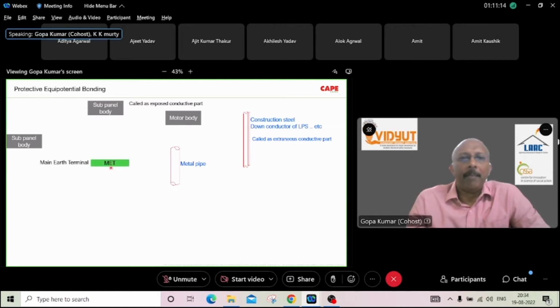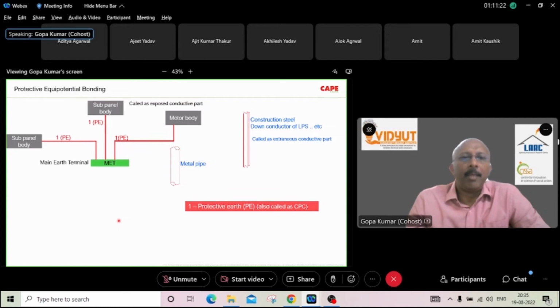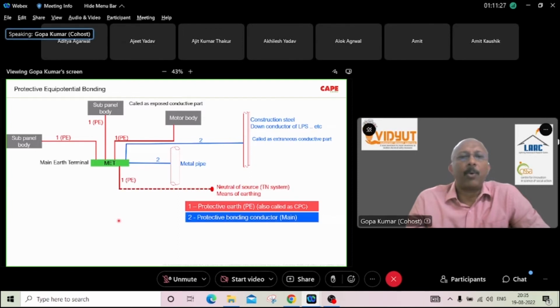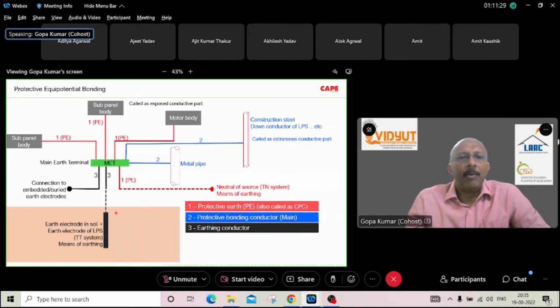You have to take a bus bar and interconnect the exposed conductive part to the MET. This is called protective earthing. Interconnect the extraneous conductive part to the MET. This is called protective bonding. Now the MET, in case of a TT system, has to be connected to one earth electrode in soil, and you should have an RCD for earth fault protection, and this is called the earthing conductor. The MET is also connected to some buried metallic items. They are also called the earthing conductor.